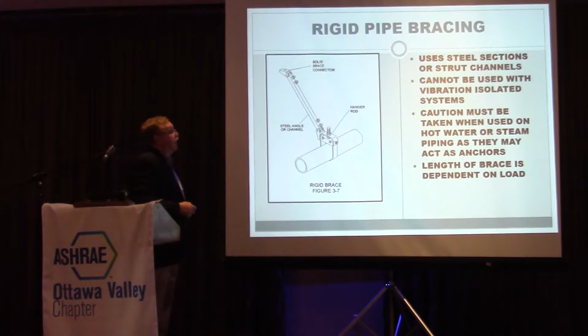One of the problems we ran into, and figured out in Northridge, was what I call the pole vault effect. Basically: I've got a rigid brace and a rod holding up this pipe, with an anchor up in the ceiling above. Earthquakes move back and forth -- you'll see that in photographs in a minute -- they move in all directions, but for this example we'll say it moves left to right. When the load goes from left to right, what happens?